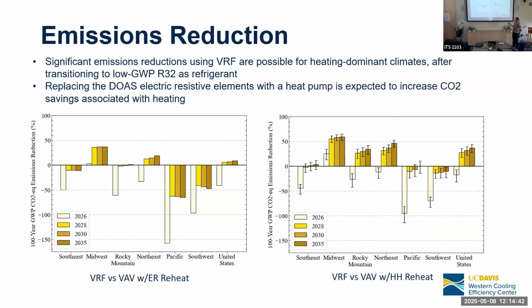And these are our results for each of the regions. If you look at Midwest and Northeast, after the transition to R32, you've got some emissions advantage in those climates because they're more heating dominant. Other places, especially like the Pacific, where electricity is lower emissions, and we don't have a lot of demand for heating, we have more demand for cooling, we don't have quite the same savings, so it's not as advantageous in those climates.